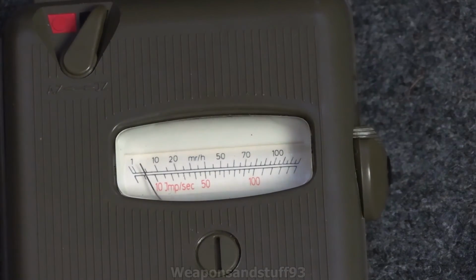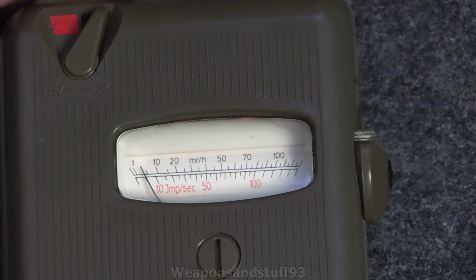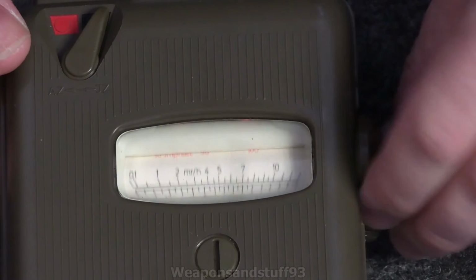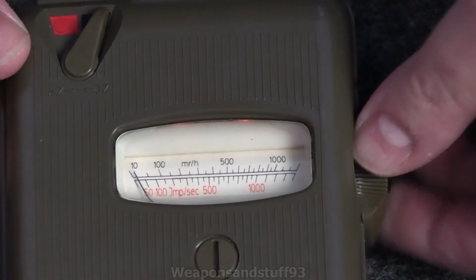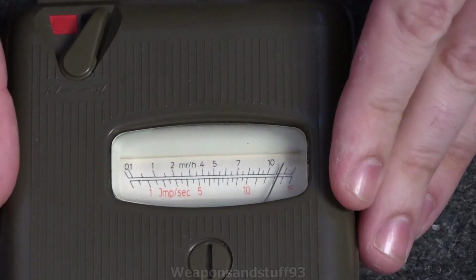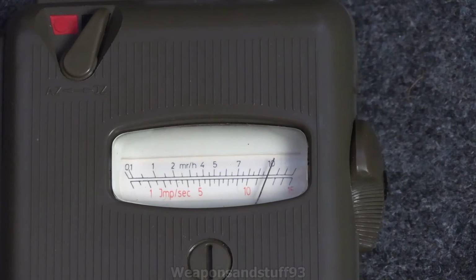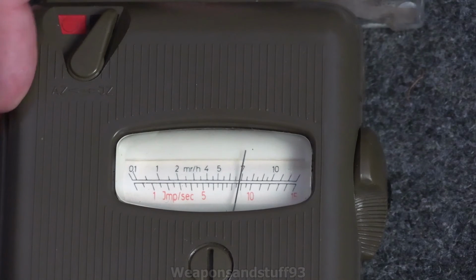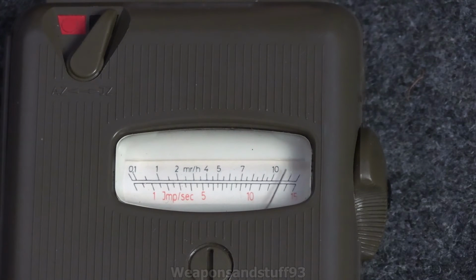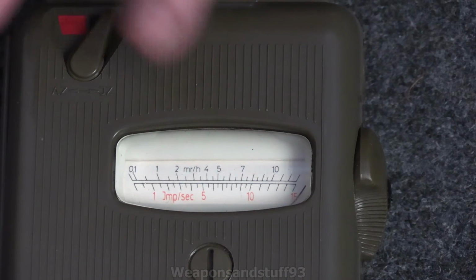Now if we just test it against the gamma only on there, you can hear some of the gammas coming through. If we go back to the lowest scale, going the wrong way again. Or am I? No, that is the right way. So it's basically off scale for the most part, with a strong radium source through the gamma alone, but obviously as soon as you open that beta window, it picks up a lot more. So let's see how high this beta tube can go.